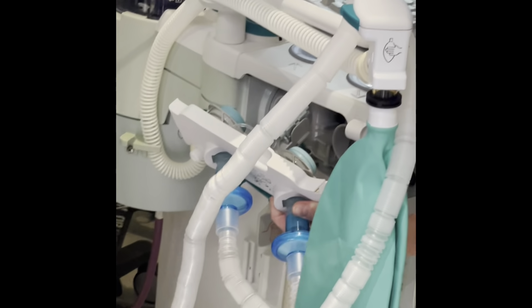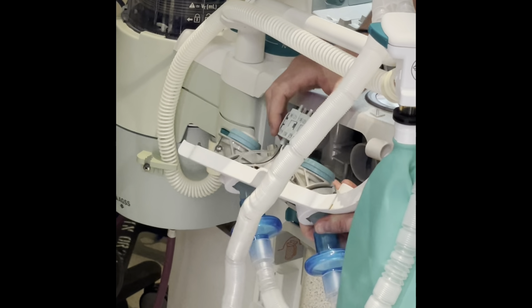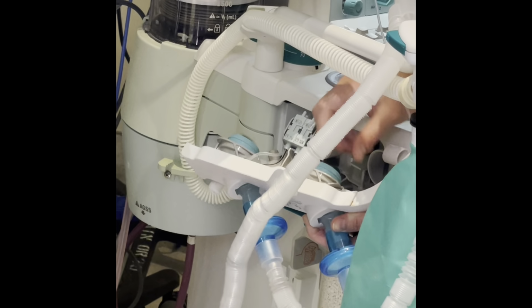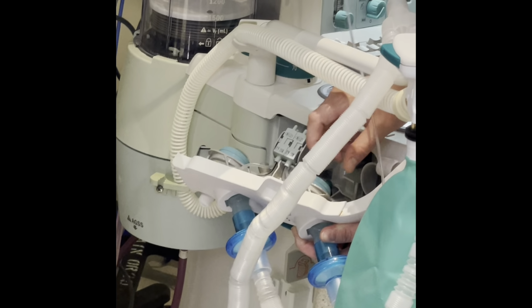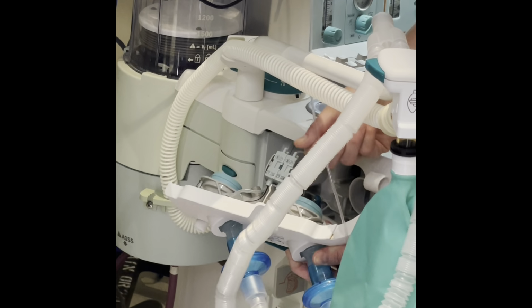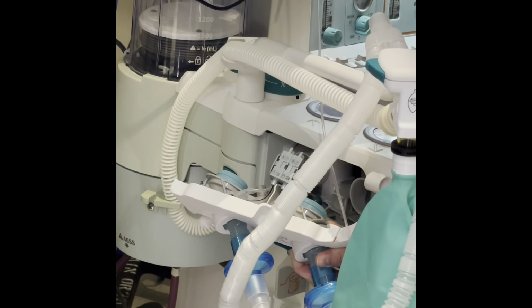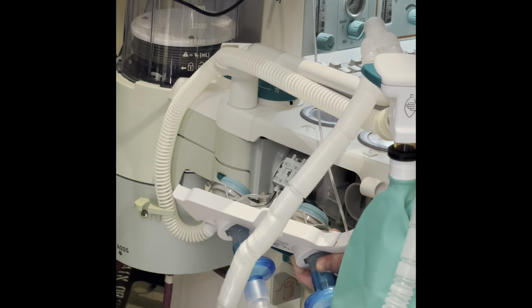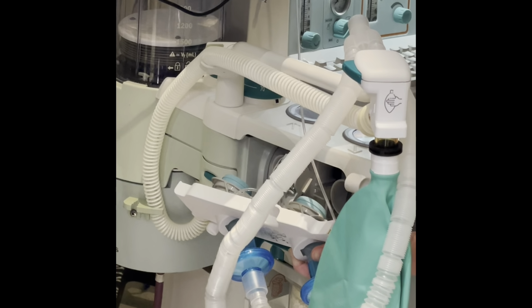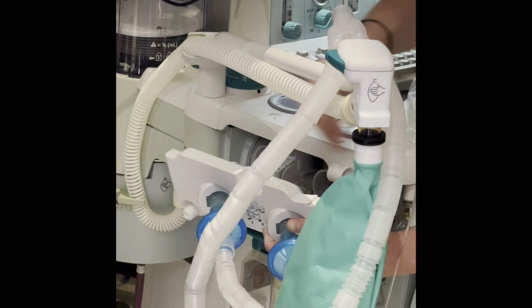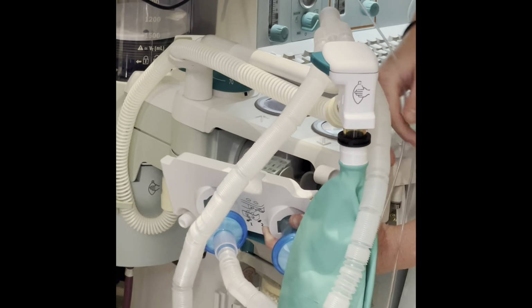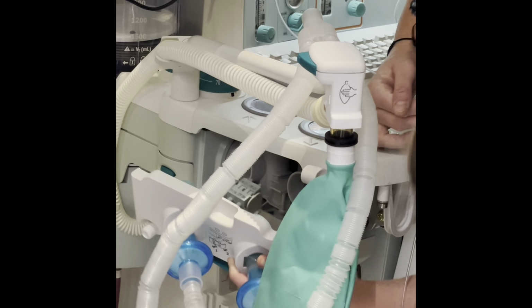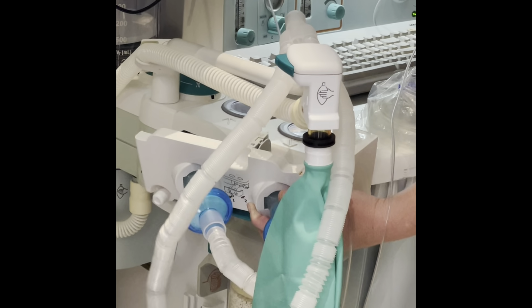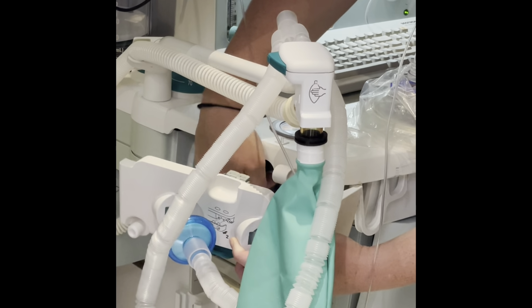This one doesn't have the... Sometimes it has a little O2 cell that you need to untwist and open to air, and that's a separate check that you do to calibrate the oxygen sensor. With this machine, you just take it out, open it to air, and then put it back in. It can be a little tricky to put back. If you want to try, I'll let you give it a shot. You just have to line this up with the thing here.